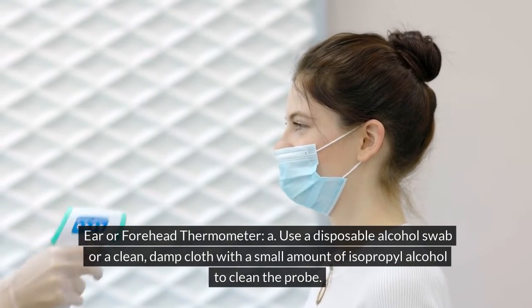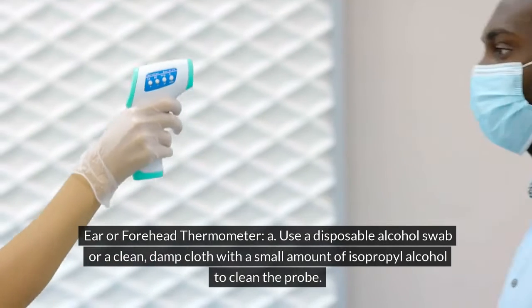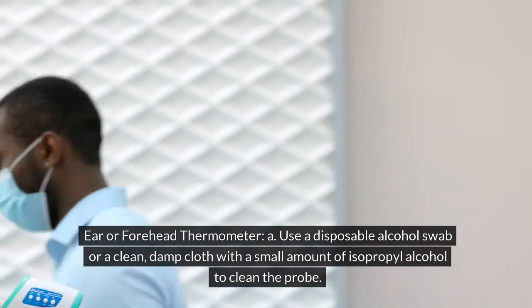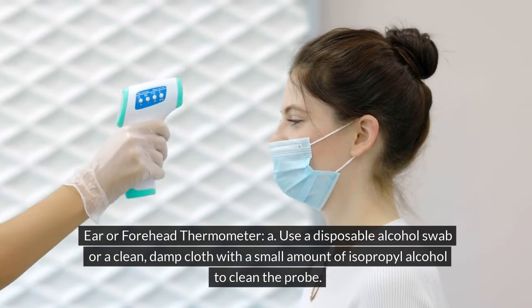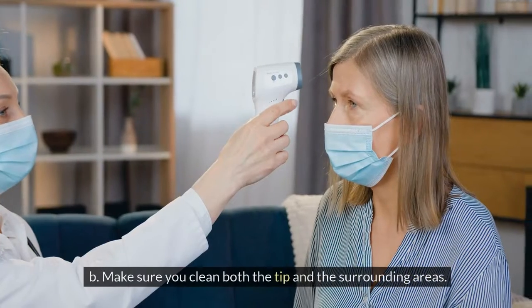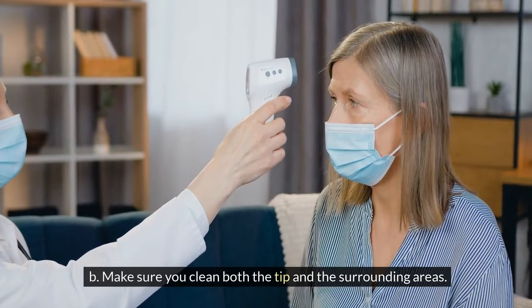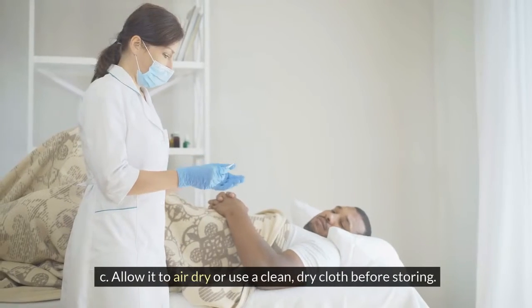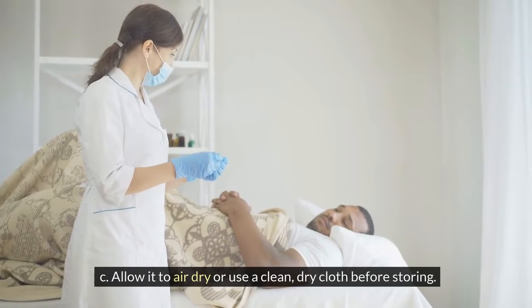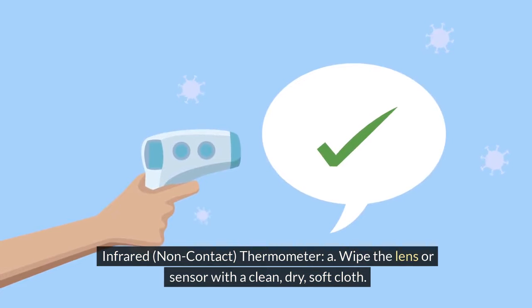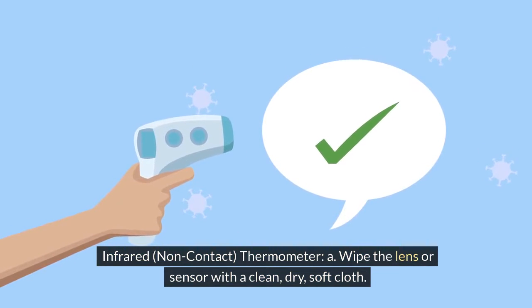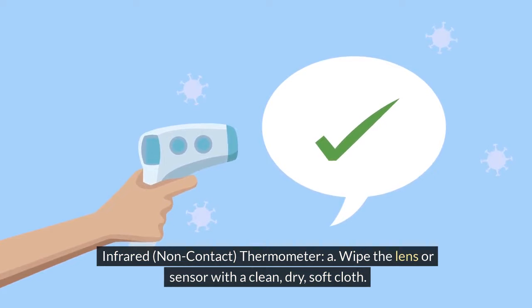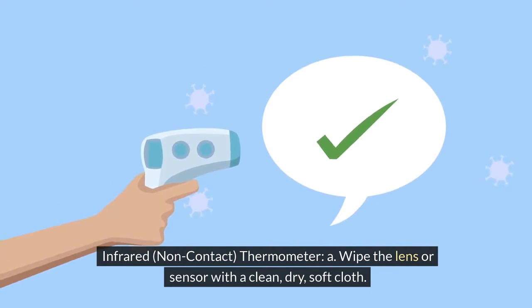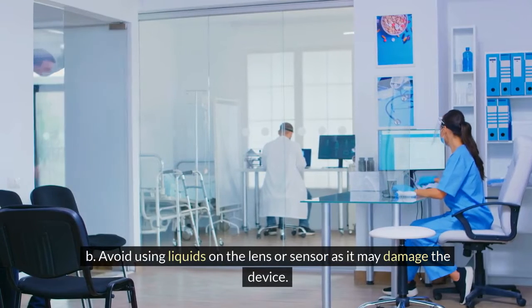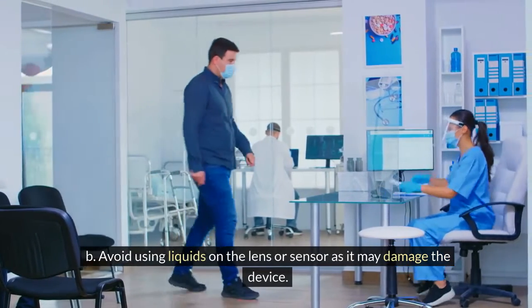Now let's look at how to clean an ear or forehead thermometer. You'll use a disposable alcohol swab or a clean, damp cloth with 70% alcohol to clean the probe. Make sure you clean both the tip and the surrounding areas. Allow it to air dry or use a clean, dry cloth before storing. Now let's look at how to clean your infrared non-contact thermometer. Step 1, you'll wipe the lens or the sensor with a clean, dry, soft cloth. Avoid using liquids on the lens or the sensor as it can damage the device.